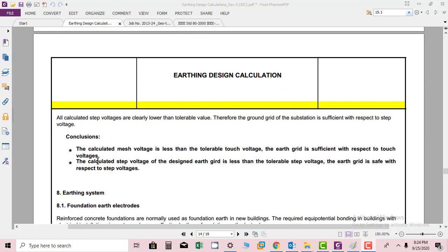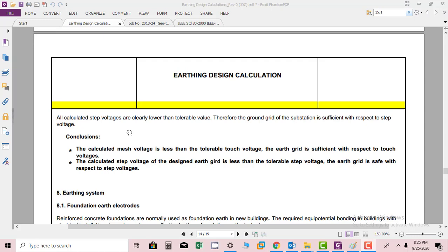Conclusion: The calculated mesh voltage is less than the tolerable touch voltage. The earth grid is sufficient with respect to touch voltages. The calculated step voltage of the designed earth grid is less than the tolerable step voltage. The earth grid is safe with respect to step voltages.